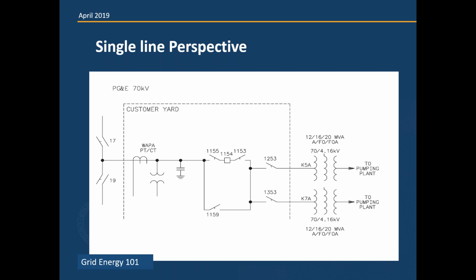Here's what we call a single line perspective. That's the same as what we just saw in the last picture. On the left side of the screen, you can see a couple of pole switches, pole switch 17 and 19. It's a 60 kV or 70 kV line. It comes in through some metering potential transformers and current transformers, so we can see how much load is flowing through there. Then 1154 is an example of a circuit breaker and a bypass disconnect. Then it swings over to the right, and there we have a couple of examples of 70 kV to 4.16 kV transformers down to the pumping plant. This is what your system operator looks at when he's going to be working on the equipment. Next slide, please.